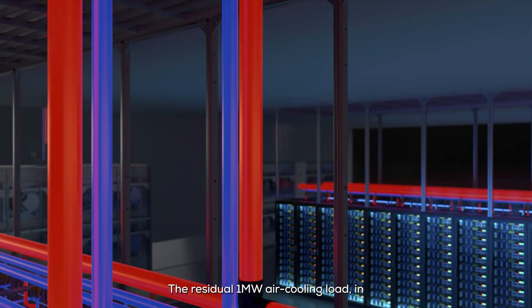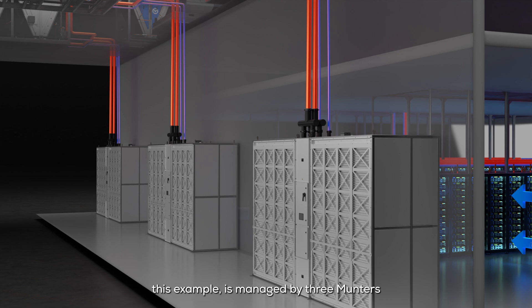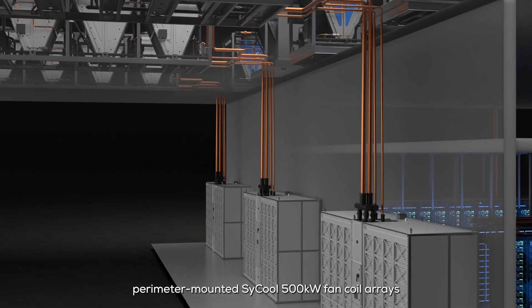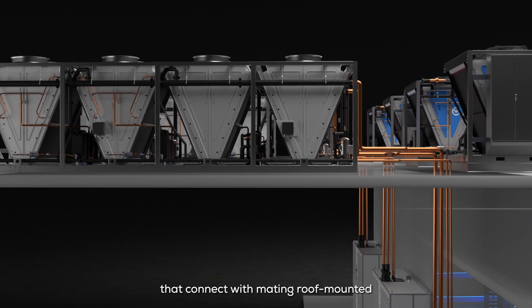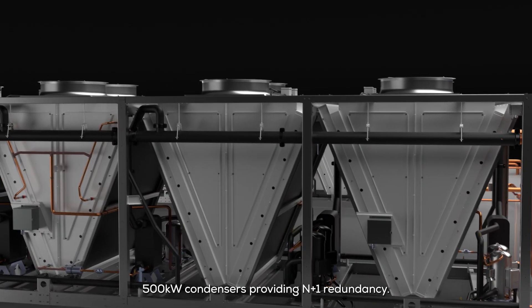The residual 1 megawatt air cooling load, in this example, is managed by three Munters perimeter-mounted SyCool 500 kilowatt fan coil arrays that connect with mating roof-mounted 500 kilowatt condensers, providing N+1 redundancy.